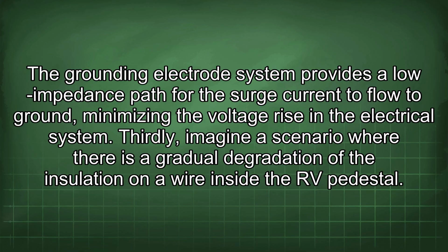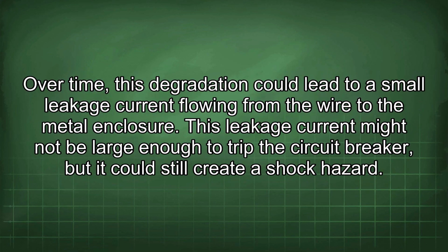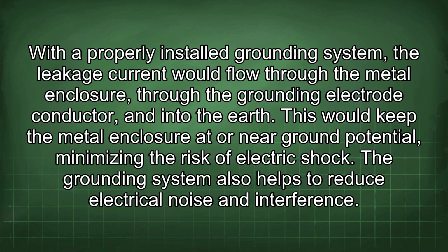Thirdly, imagine a scenario where there is a gradual degradation of the insulation on a wire inside the RV pedestal. Over time, this degradation could lead to a small leakage current flowing from the wire to the metal enclosure. This leakage current might not be large enough to trip the circuit breaker, but it could still create a shock hazard. With a properly installed grounding system, the leakage current would flow through the metal enclosure, through the grounding electrode conductor, and into the earth. This would keep the metal enclosure at or near ground potential, minimizing the risk of electric shock.